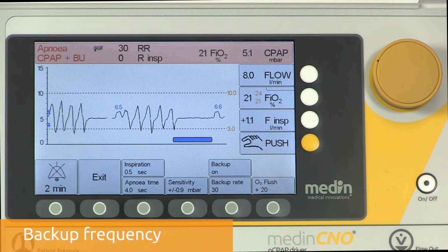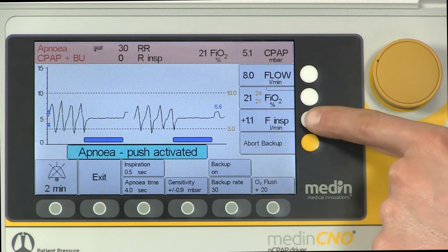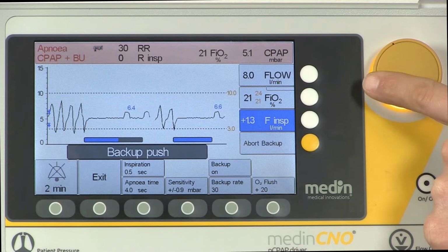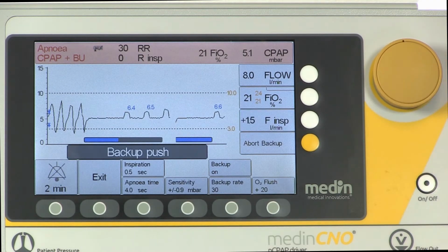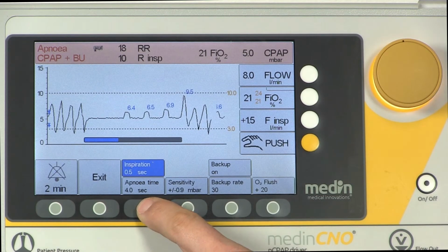The backup frequency can range between 10 and 120 breaths per minute. The rate for the backup frequency depends on the selected inspiratory time.